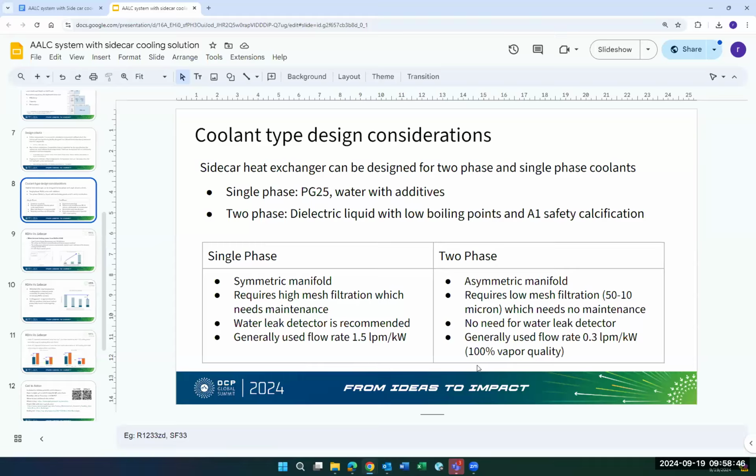The only way to detect a leak in the dielectric liquid that is evaporating is by monitoring the buffer side, the liquid in the buffer, because the vapor immediately evaporates. There are no drops or anything. Even CDUs have leak detectors. Safety is number one in data center applications, and I think no one will accept a system without a leak detector. But that's my opinion.